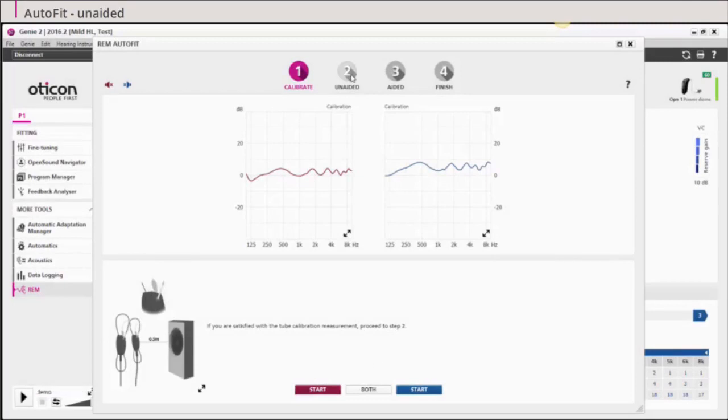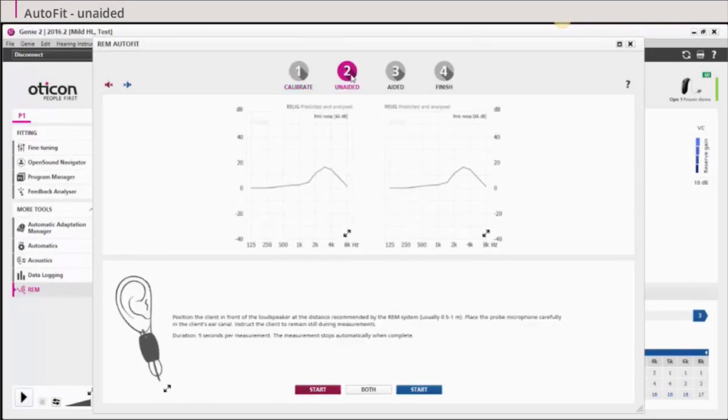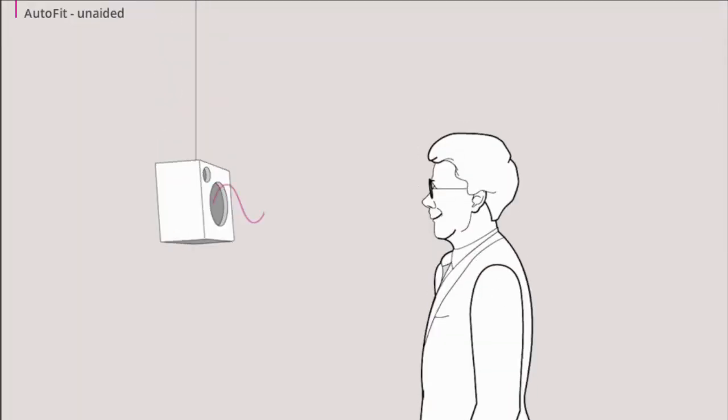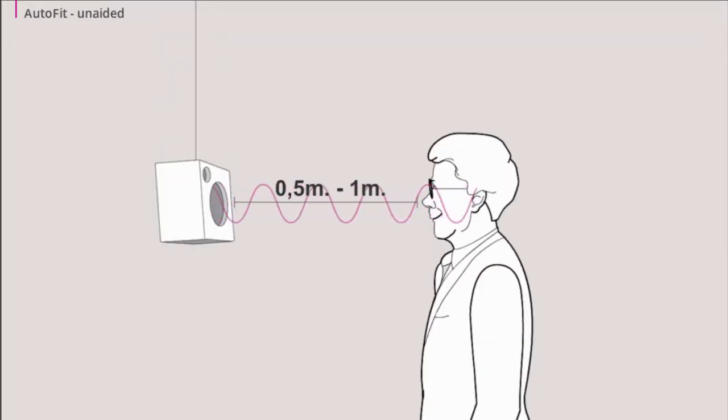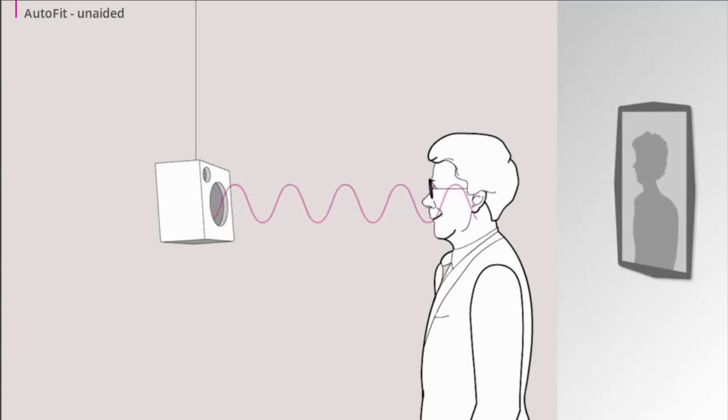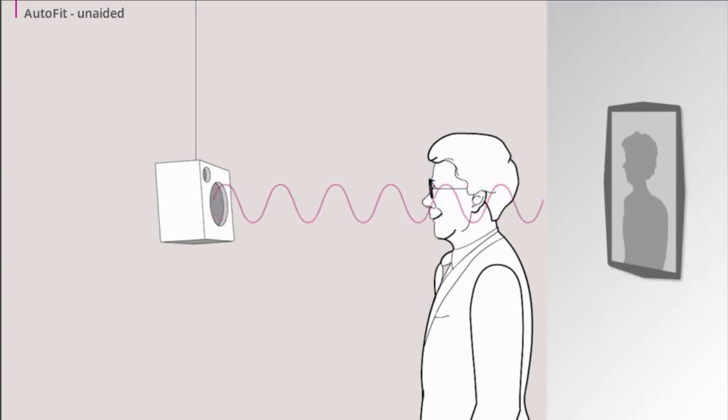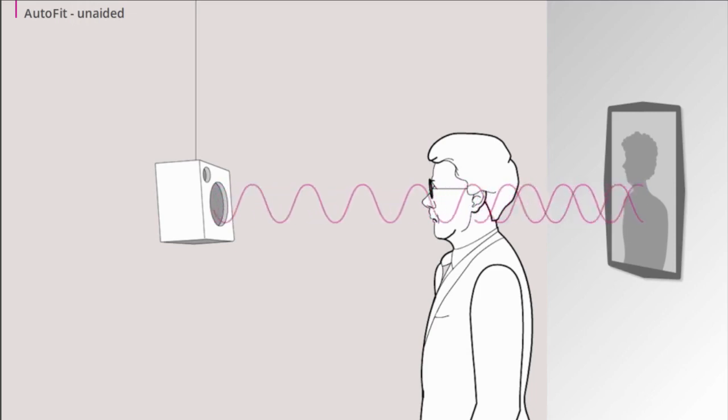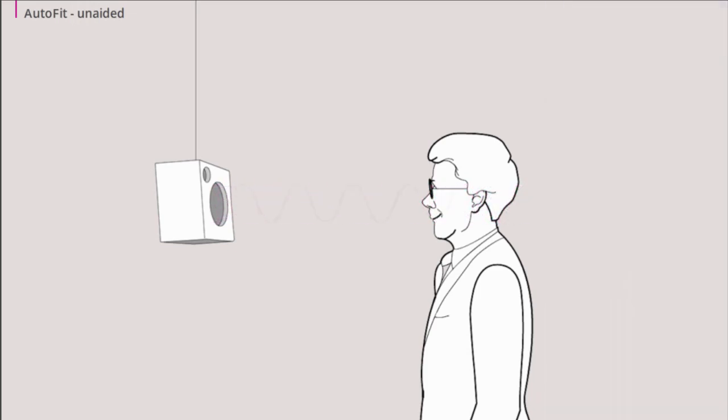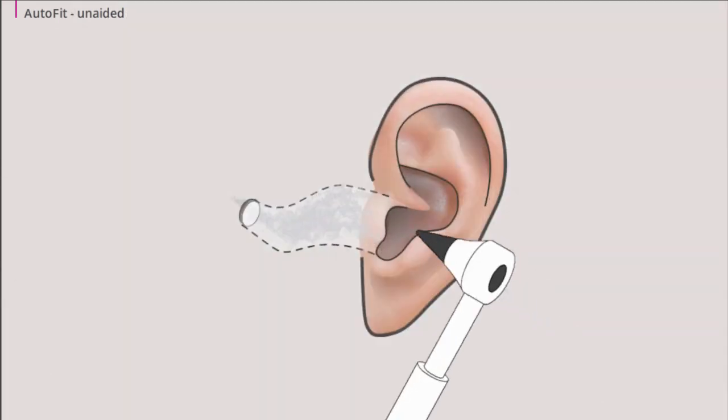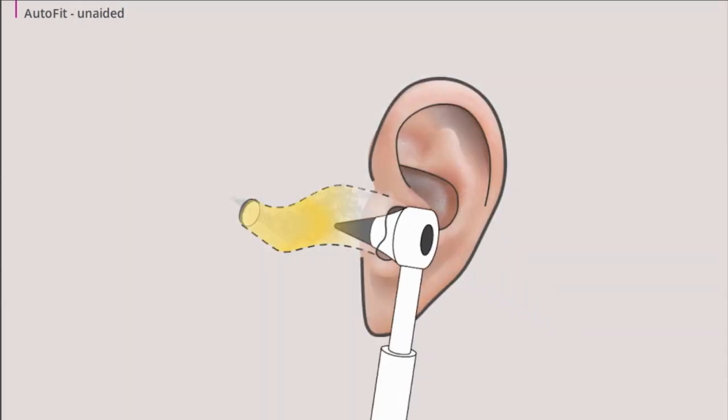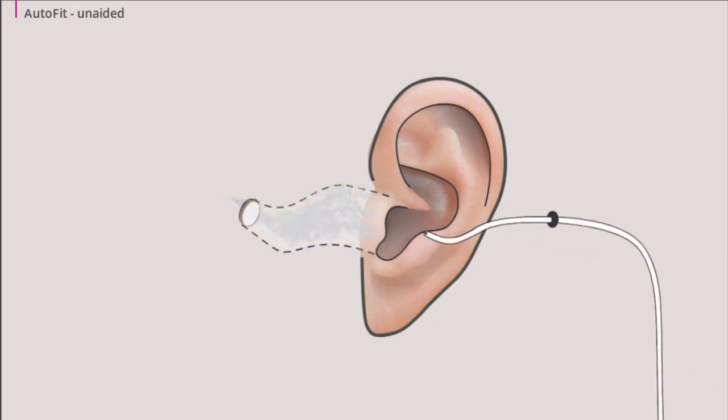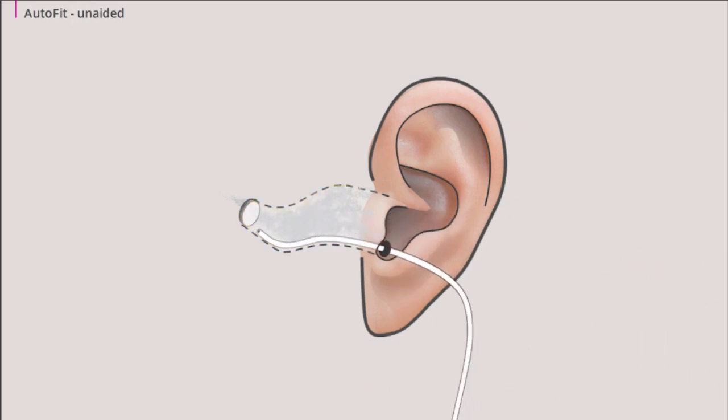Click 2, unaided. Place your client facing the loudspeaker at a distance of one-half to one meter or yard. The loudspeaker should never face a wall since it will reverberate the signal. Perform an otoscopy to secure the ear canal is clear. Then place the probe tube in your client's ear canal. The probe tube should be placed within 6 millimeters or a quarter of an inch of the tympanic membrane.